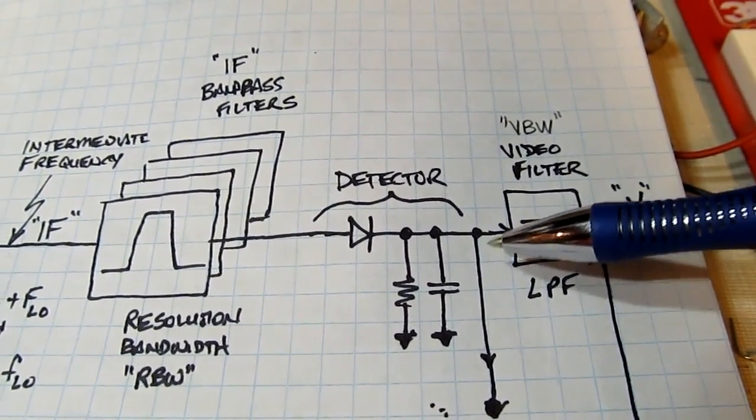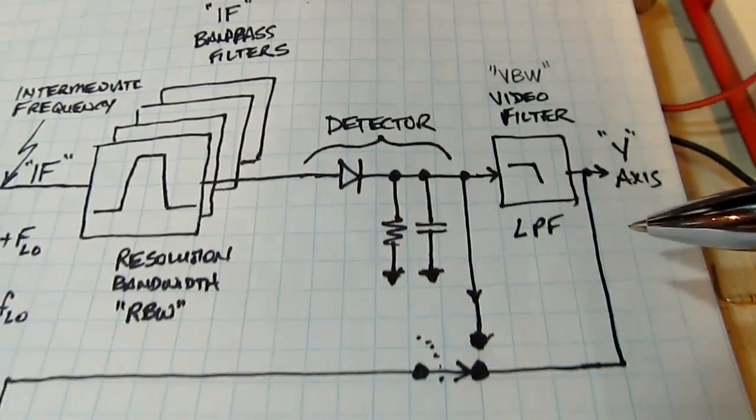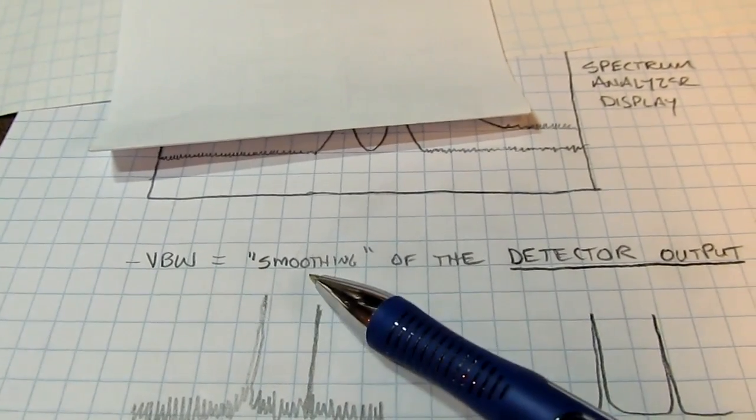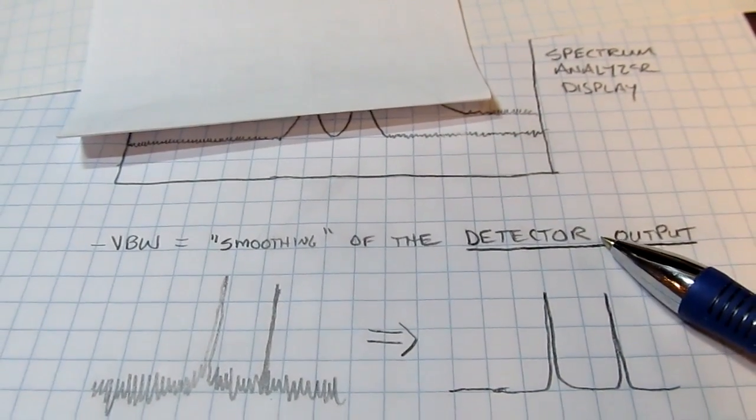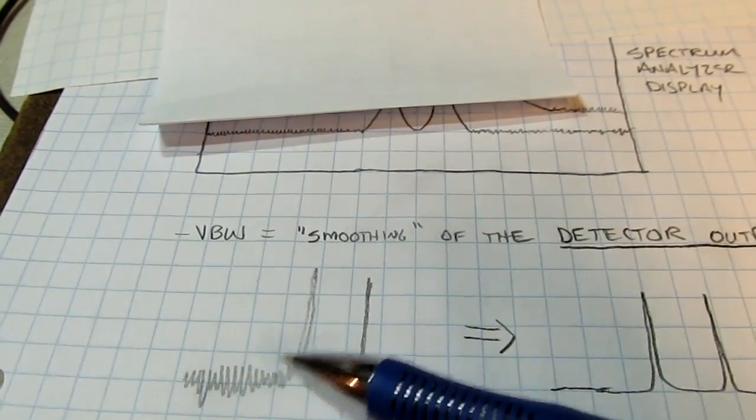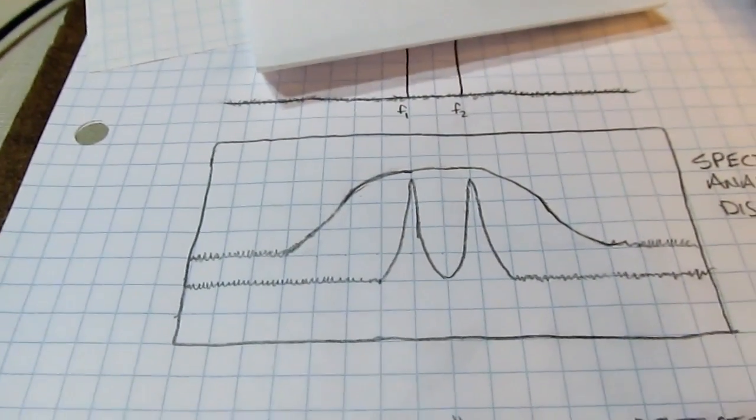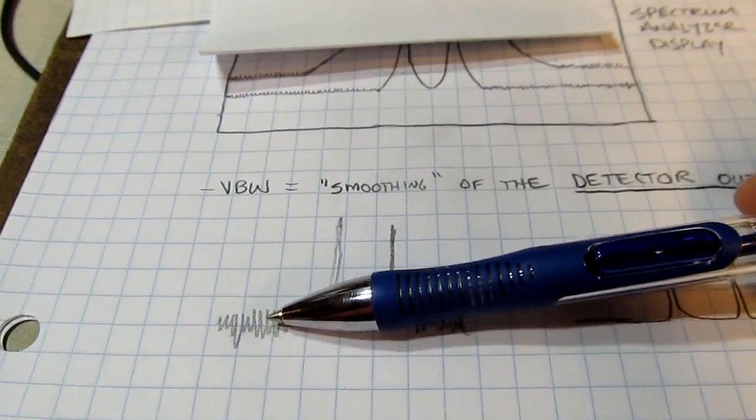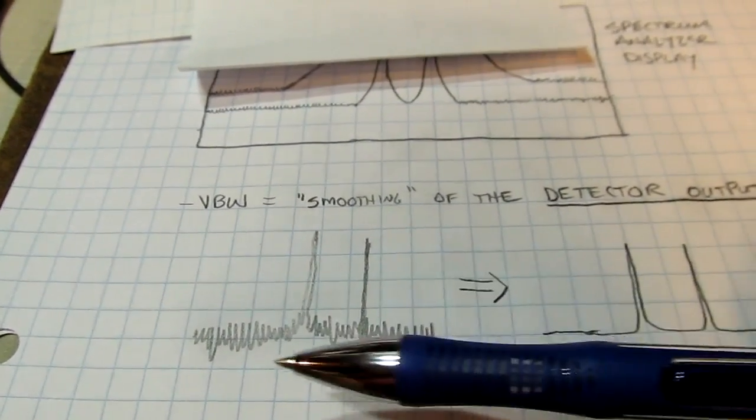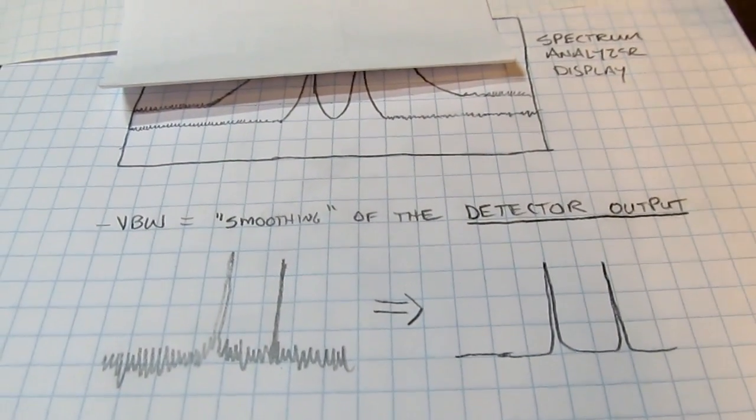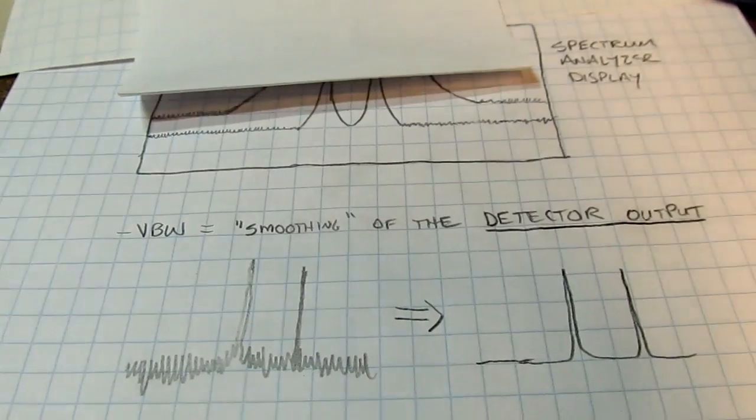The video bandwidth filter, or the video filter, essentially reduces the amplitude of that noise. And it really just has the effect, effectively, of smoothing the output from the detector. So the video bandwidth is really a smoothing filter, in a sense, of the detector output. It will not have any effect on the level of the noise, like the resolution bandwidth did. It's only going to have effect, essentially, on the peak-to-peak magnitude of it. So it can smooth the trace out to make it easier to measure where the noise floor is.